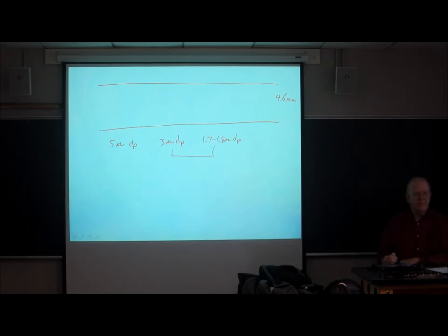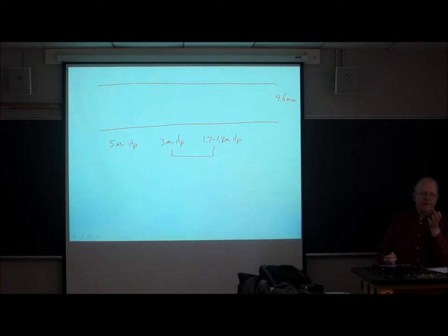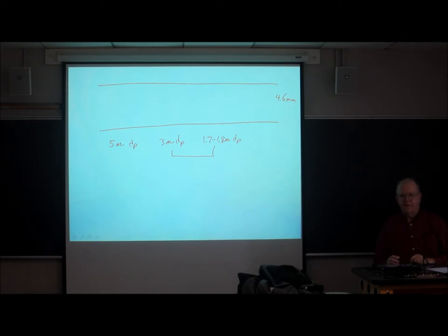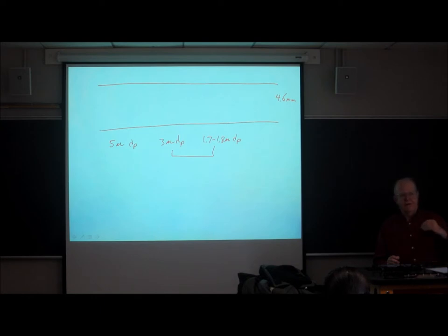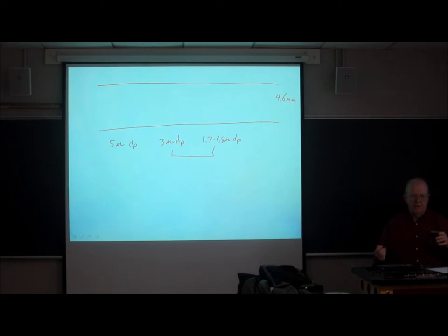Somewhere between 5 micron and sub-2-micron, we crossed a very serious boundary. The instrumentation available up to about 5 years ago had a pressure limit of about 5 to 6,000 PSI — roughly 400 bar. When the sub-2-micron barrier was breached, 400 bar just didn't cut it, and companies started introducing very high pressure systems on the order of 800, then 1,000, then 1,200 bar.